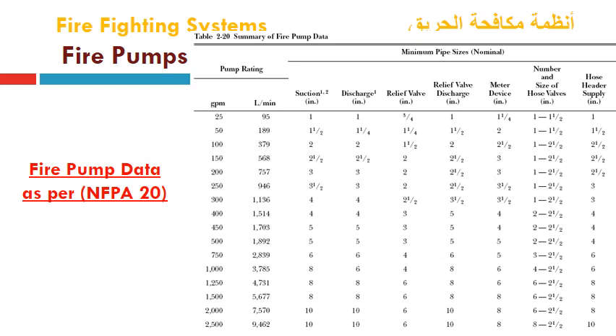Finally, this slide presents a summary of fire pump data, table 2-20, which indicates all the recommended diameters in inches and their nominal minimum pipe sizes for different pump ratings, starting from 25 GPM, 50, 100, 150, 200, 250, 300, 400, 500, 750, 1000, 1250, 1500, 2000, 2500. The flow is also shown in liters per minute in this column, which is equivalent to the GPM in the British system as a pump rating.